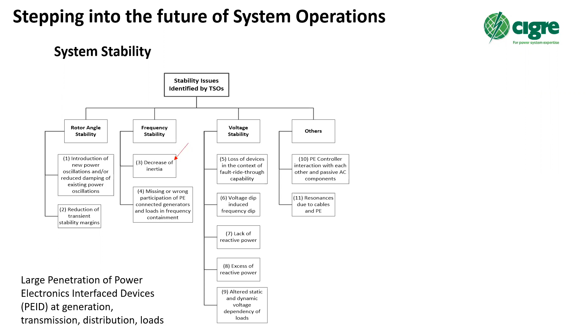In the next graph you see the effect of the amount of inertia, characterized as the energy stored in rotating masses, on how frequency behaves after the loss of generation, taking into account primary control and load reaction. The lower the inertia in the system, say 100 gigawatts, the higher the transient in frequency, which can activate relays and even lead to collapse.